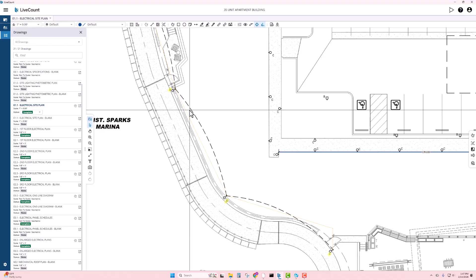Going to the first floor, branch wiring for all of the fixtures, and I used a mix of 12-2 and 10-2 Romex. One thing I wanted to mention is you see these yellow orange marks right here. Well, these weren't fully coordinated electrical drawings. The heat pumps on the roof were not on the electrical drawings, so they were in the panel schedules. And the fan coils were not shown on the electrical drawings either.